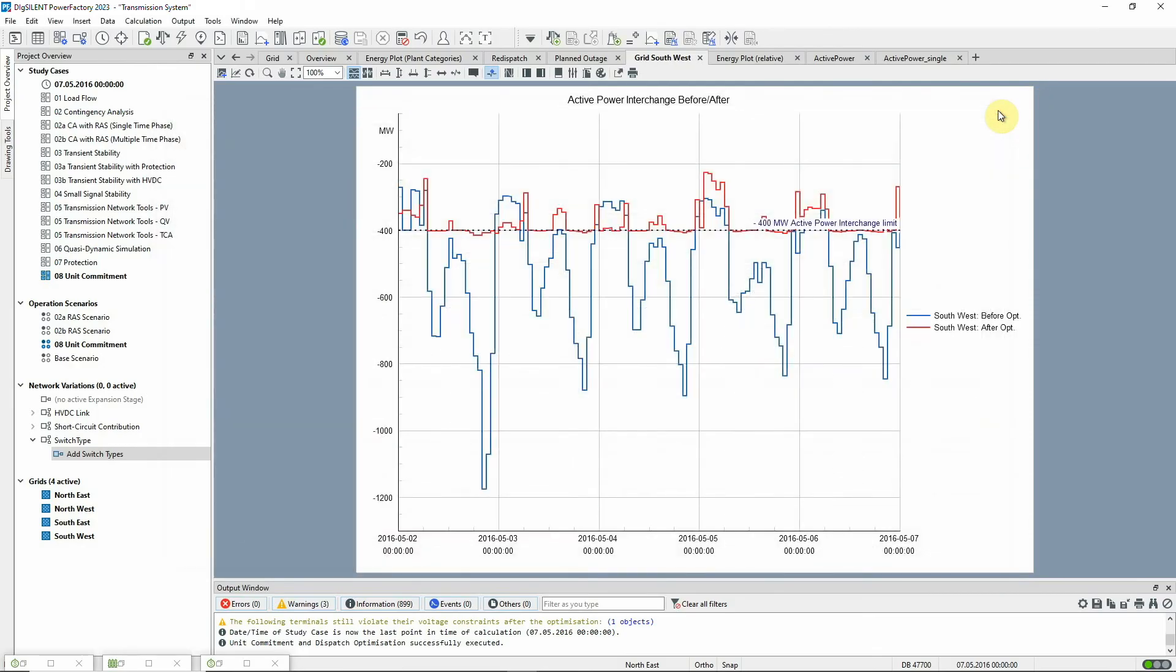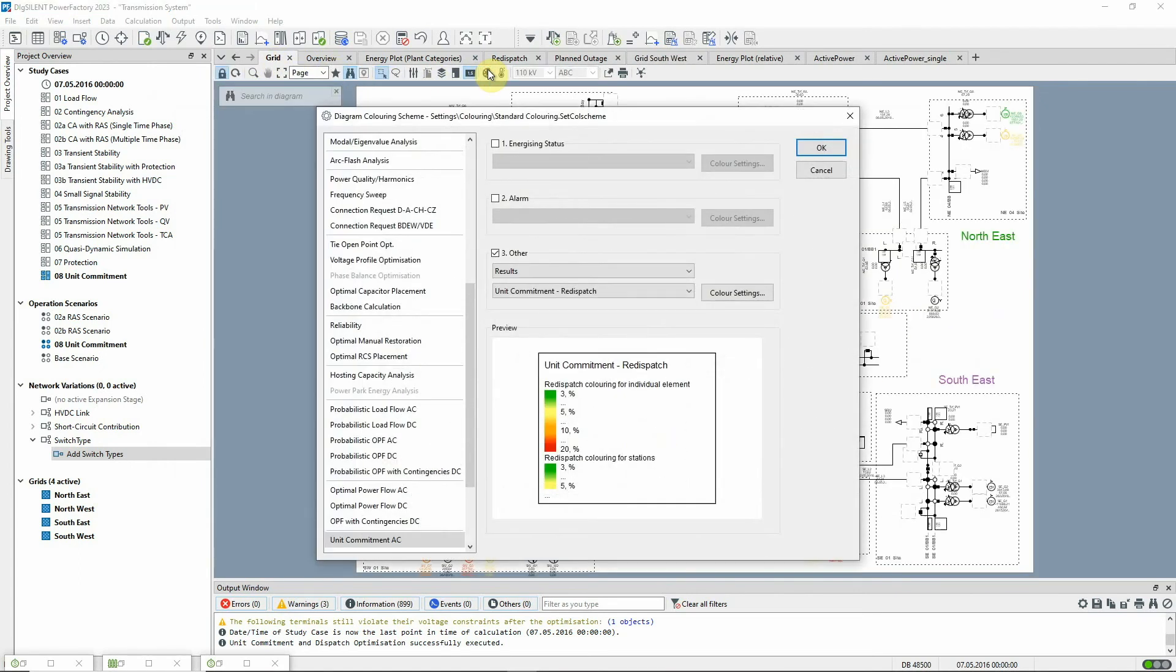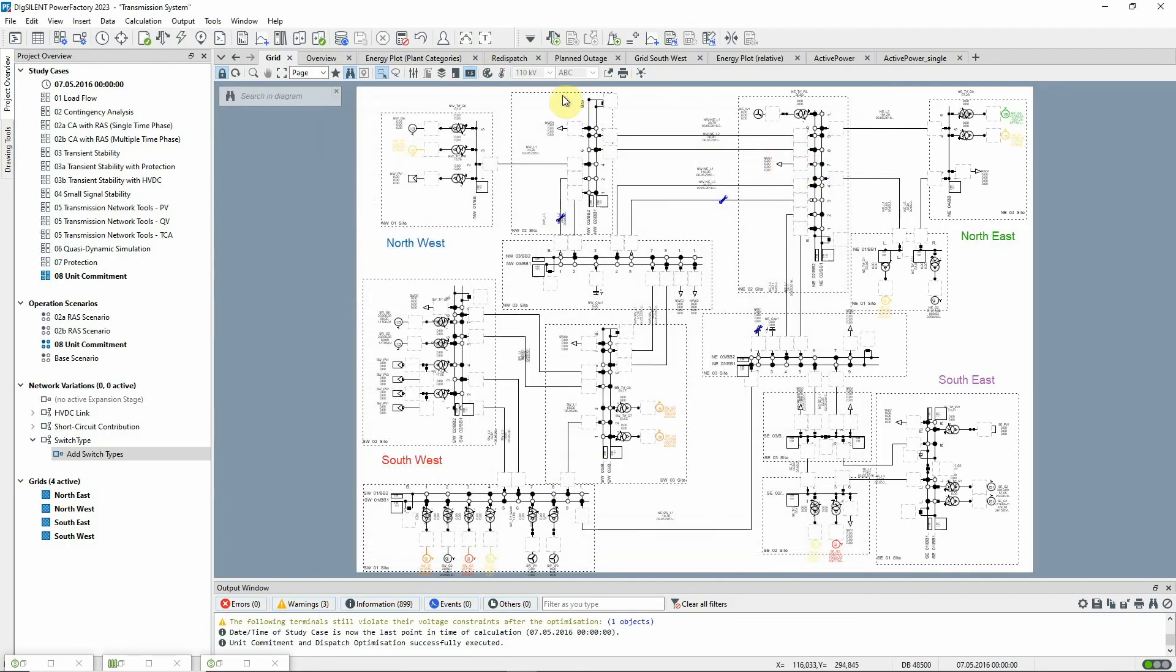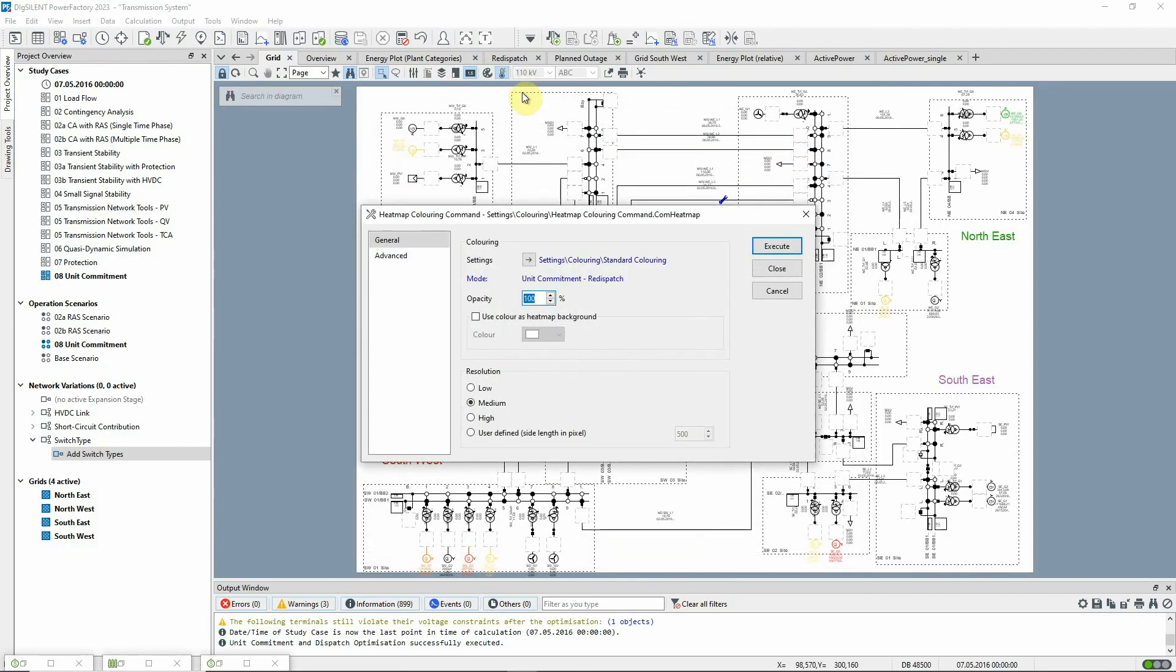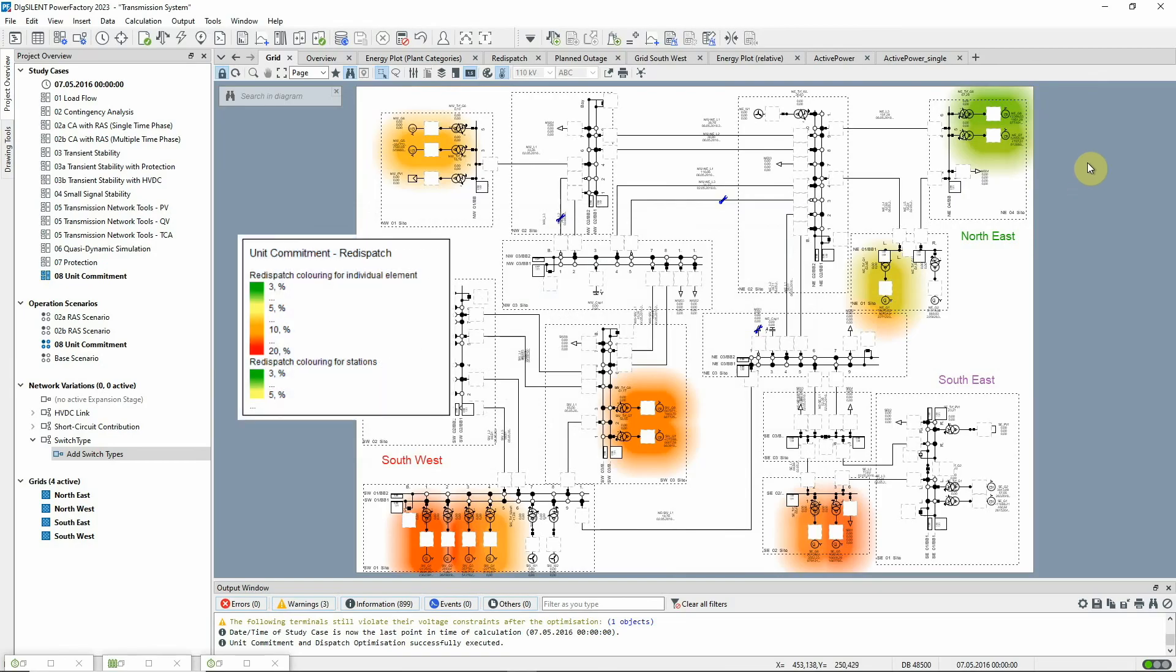We can also use diagram colouring to see immediately whereabouts in the network the redispatch energy or redispatch costs are incurred. Redispatch costs are the costs associated with the generation changes compared with the default quasi-dynamic solution which have been made in order to minimise overall costs.